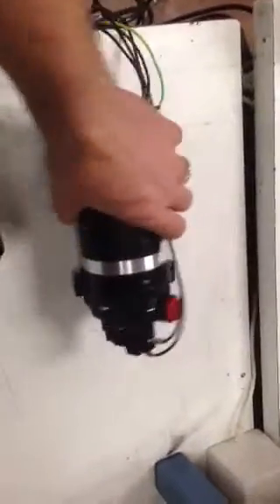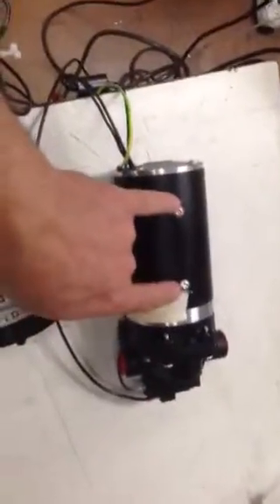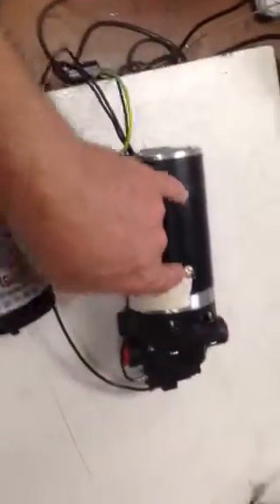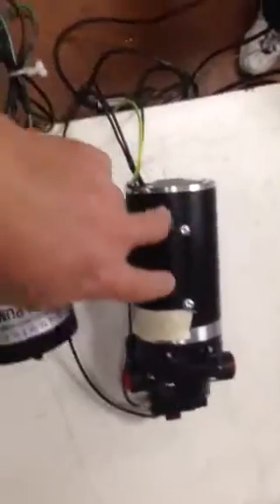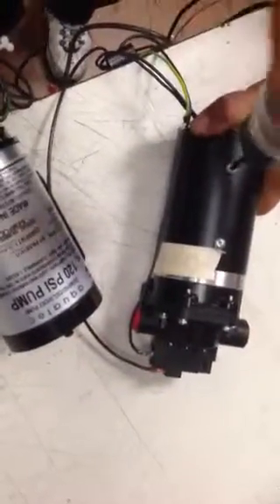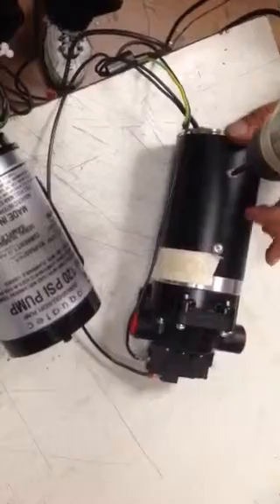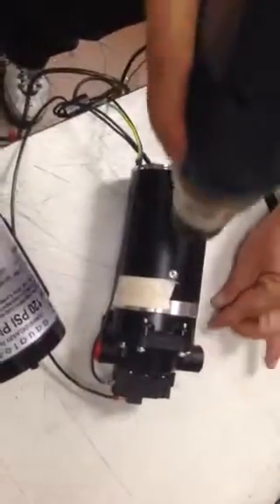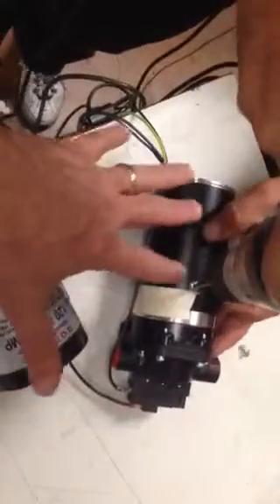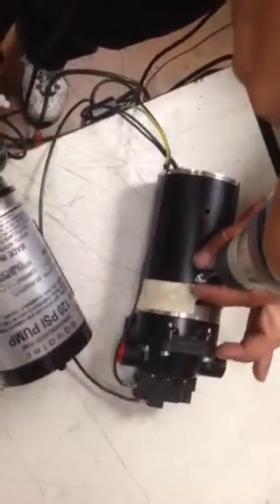Now we have the pump head attached to the new motor. The only thing left will be the parts you have there for the mounting plate. We can go ahead and we'll show you how to do that. These two bolts, in this case they're on the motor, but you may just have some empty holes there right now. We're going to remove these bolts. Again, these two holes are going to be empty. You're not going to have any screws therein. This is how you're receiving the motor.